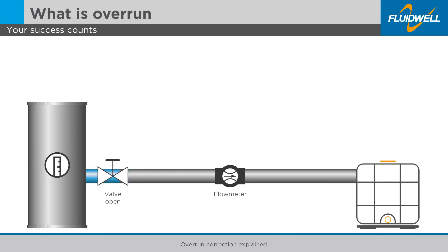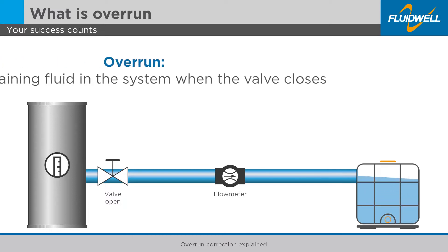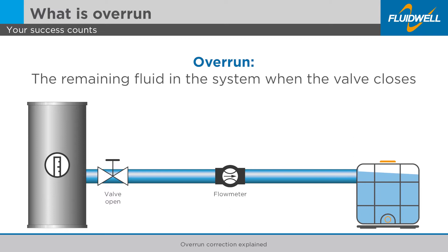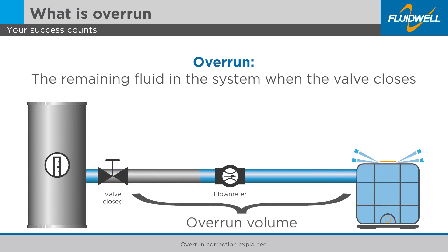An overrun may occur in a batch control process when the batch ends and the control output deactivates the pump or valve. The remaining fluid in the system that has already passed will be added to the batch, causing an inaccurate batch volume.